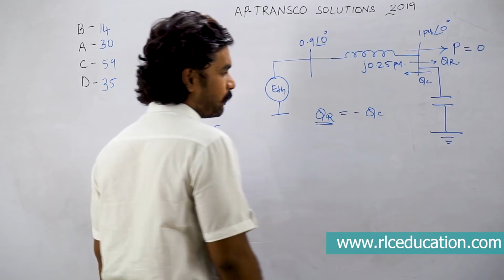Next we will see what is the reactive power received on bus number 2, let us say that is QR. By looking at this, I can say the reactive power received from the source is equal and opposite to the reactive power supplied by the capacitor bank. So if I find QR and take the minus of that, I get the power supplied by the capacitor — that is what the required MVR supplied by the capacitor bank is asking.